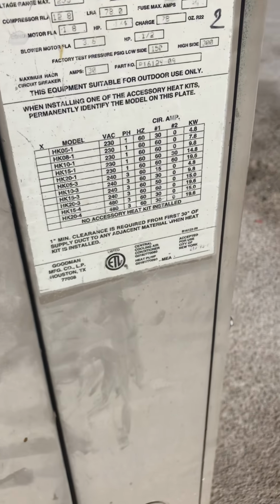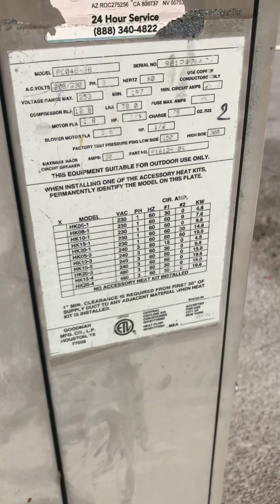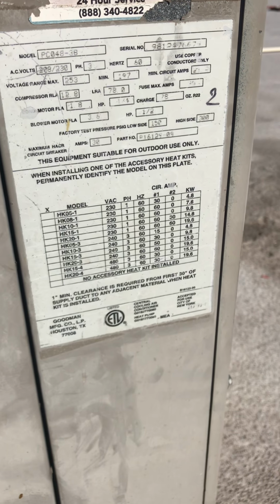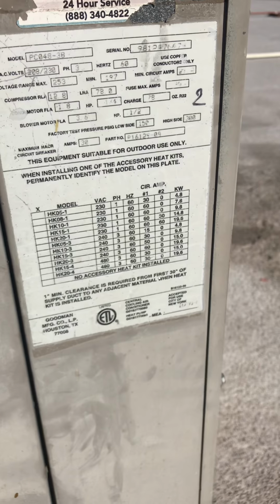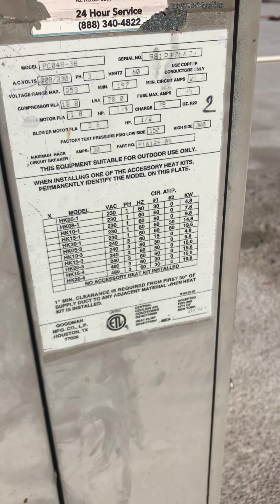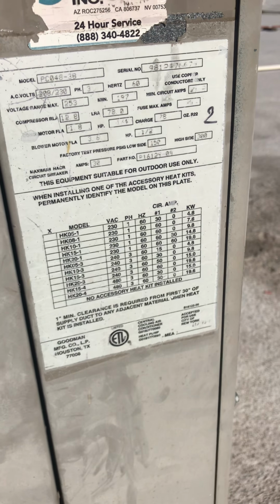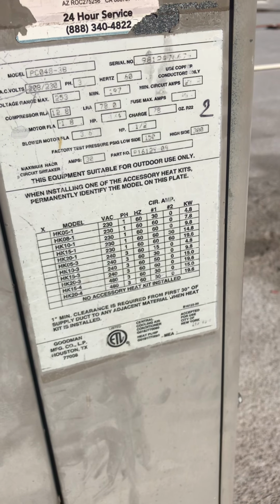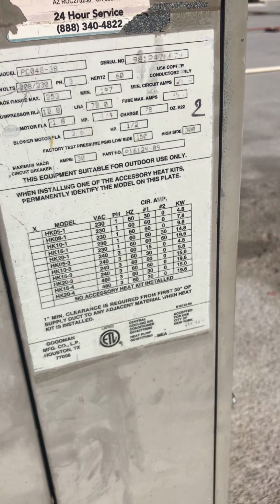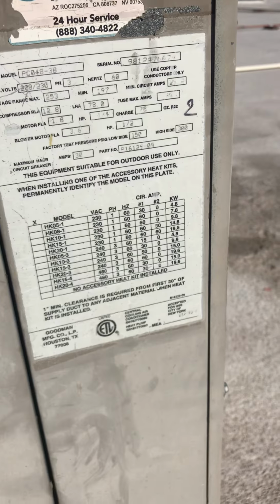Over here on the side is the unit nomenclature. You can see the model number and serial number right there. It's a 4-ton, 230 volt, 3-phase unit, looks like it's going to need a 40 amp disconnect. Minimum ampacity is about 27.2, so that'll be easy to size up.